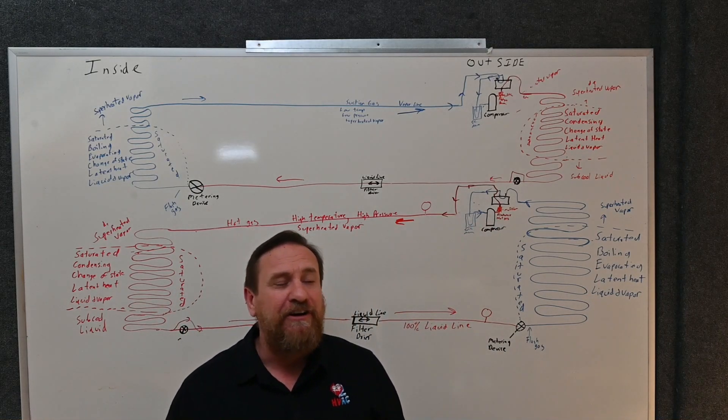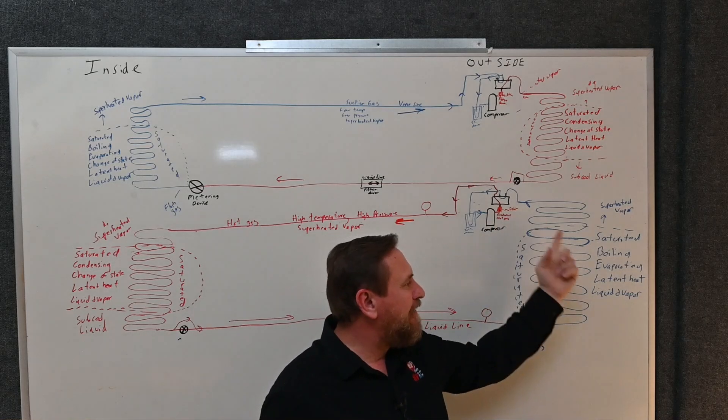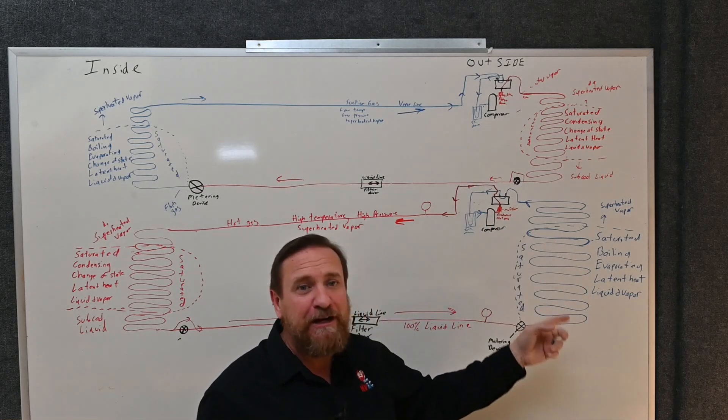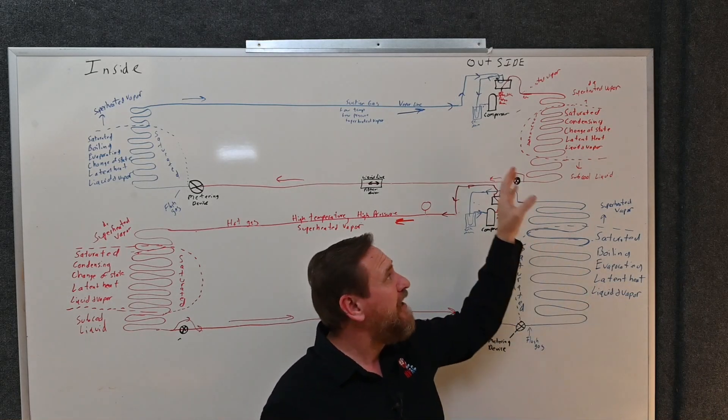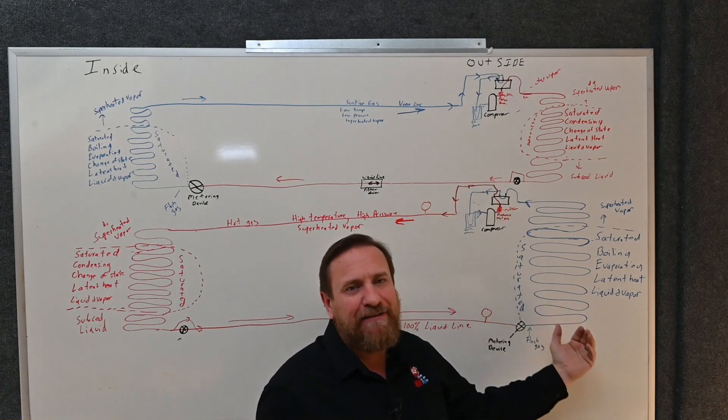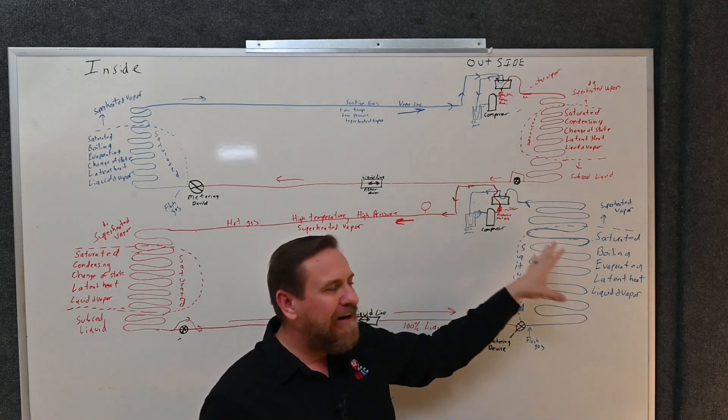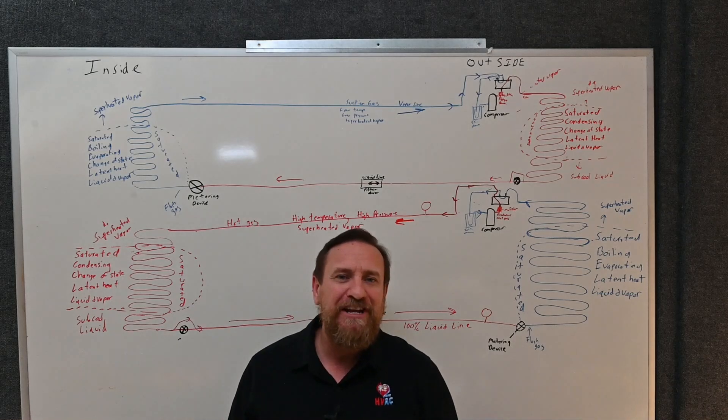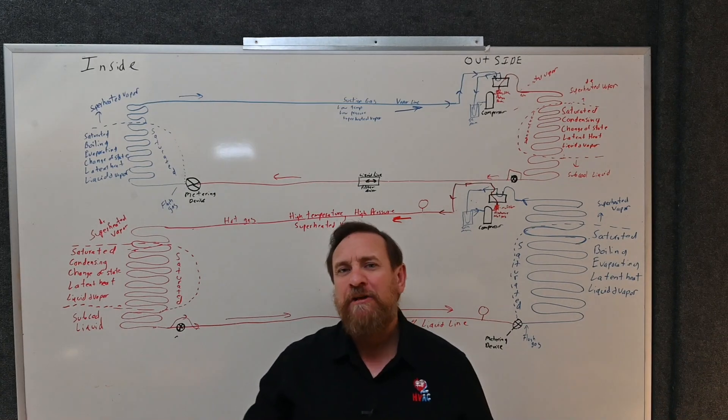Next thing you know you're out there for a service call. You put it in AC mode and there's just enough refrigerant flowing through there because the outdoor temperature is low enough that in AC mode it tends to be working. You go back to heat pump mode and now it's not working. So that's usually the rare side, but it's becoming more of an issue with microchannel systems.